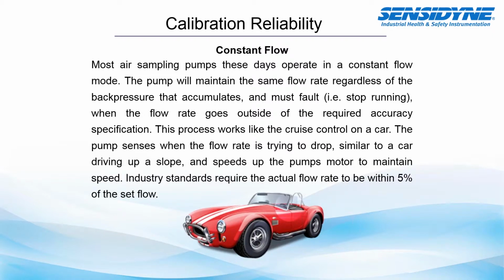So for constant airflow, most air sampling pumps these days operate in a constant flow mode. This means that the pump will maintain the same flow rate regardless of the back pressure that accumulates. And then it must stop running when the flow rate goes outside of the required accuracy. This process works a lot like cruise control on your car. The pump will sense when the flow rate is trying to drop, similar to a car driving up a slope, and it speeds up the pump's motors to maintain the desired speed or set flow rate.